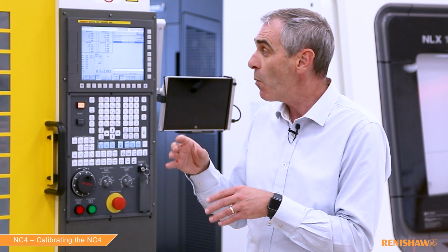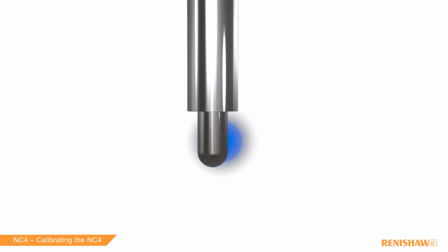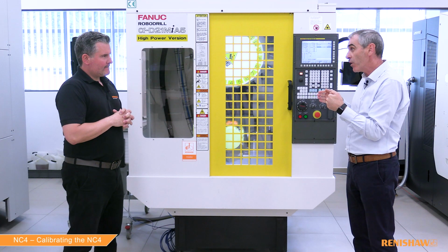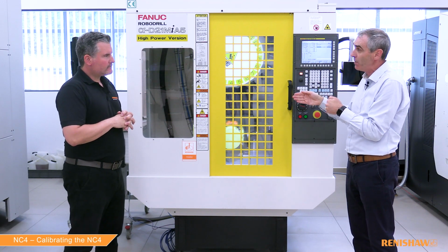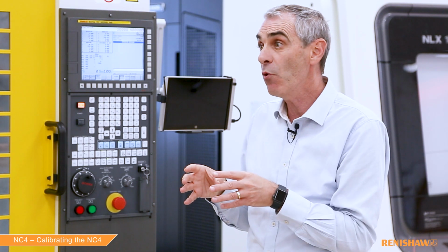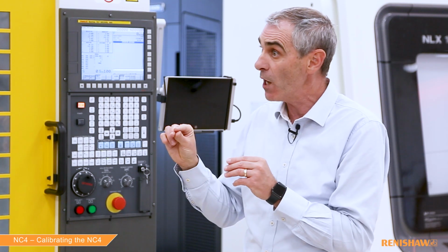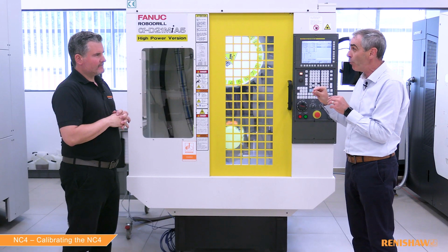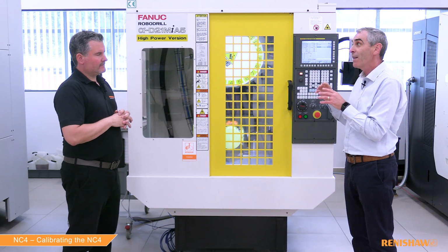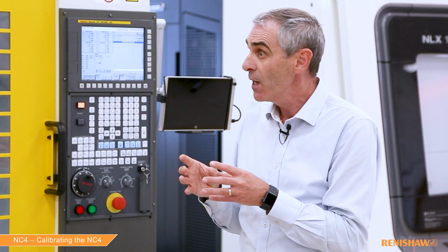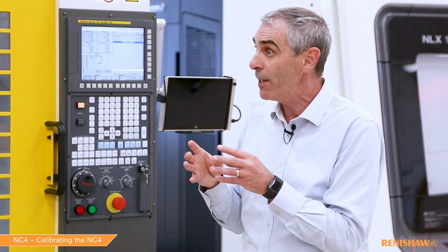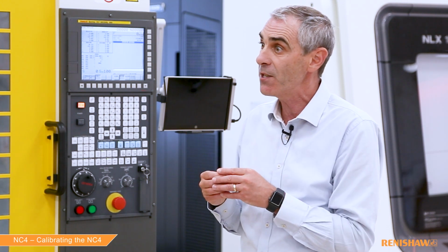So what we're going to do is, when the process is running, we're actually going to store the top of the beam, the bottom of the beam, the left-hand side of the beam, and the right-hand side of the beam. And we're also going to store a position along the beam where measurement takes place. Additionally, we're also going to store two small timer values, okay, which are very, very important for how the software runs. So calibration is very, very important because all those values need to be set up accurately to get a very good performing system.